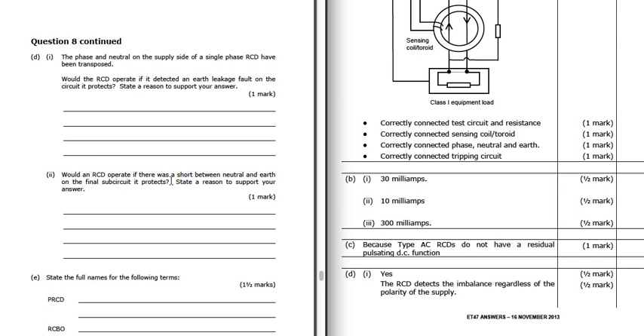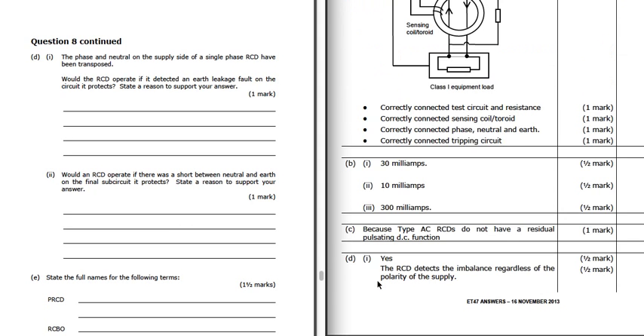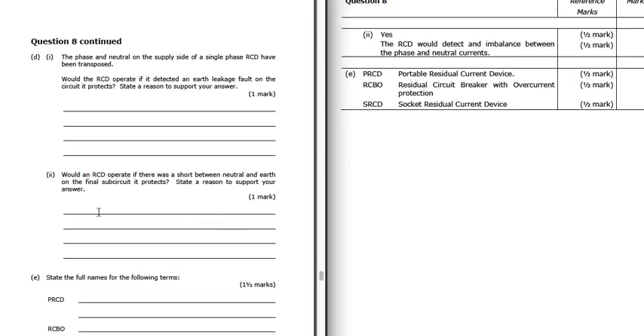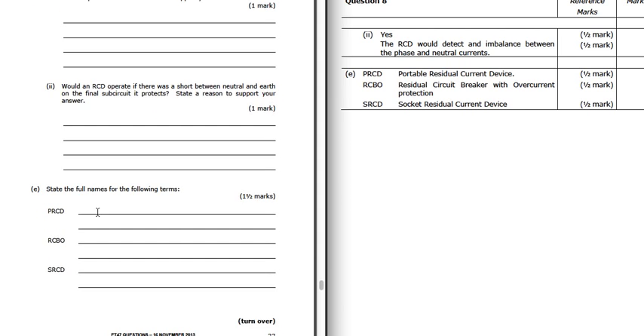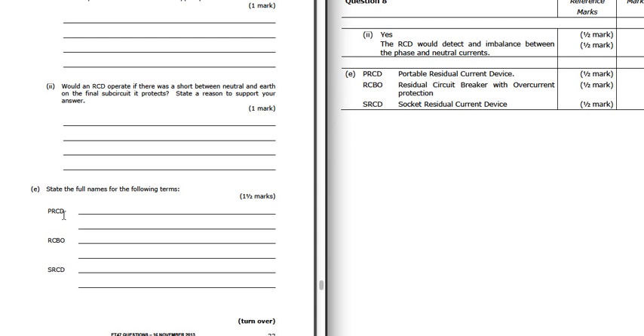Would the RCD operate if there was a short circuit between neutral and earth? I'd say yes, because it's looking for an imbalance, and if that neutral current is leaking to earth, then there's going to be an imbalance between phase and neutral again, and so it's going to operate. Different types of RCD, so there's PRCD, the portable residual current device, the residual circuit breaker with overcurrent protection, and the socket residual current device.